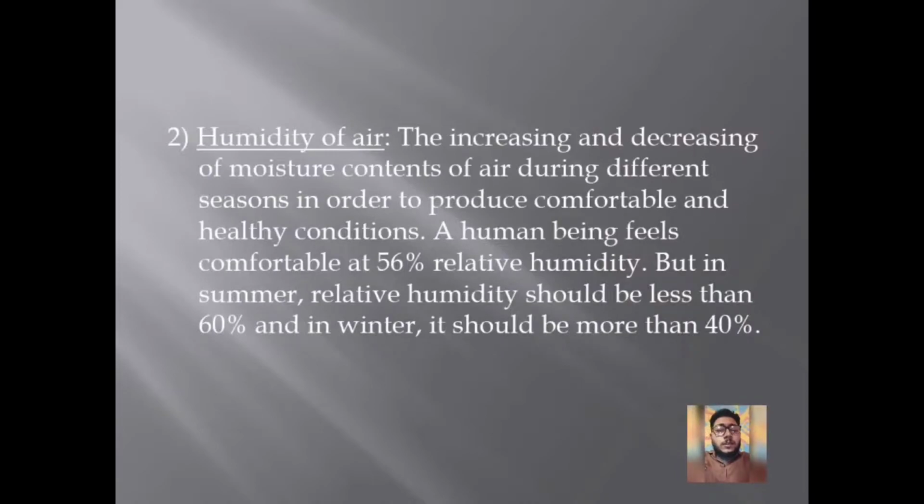Humidity of air: the increasing and decreasing of the moisture content of air during different seasons in order to produce comfortable and healthy conditions. A human being feels comfortable at 56% relative humidity. But in summer, relative humidity should be less than 60%. In winter, it should be more than 40%.